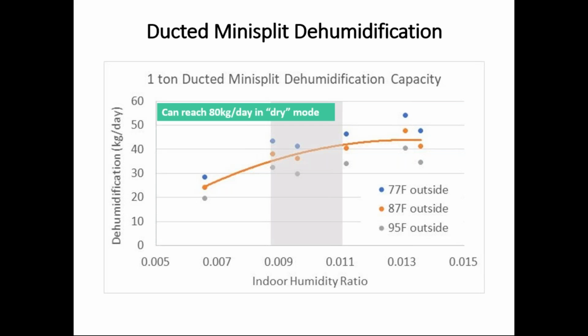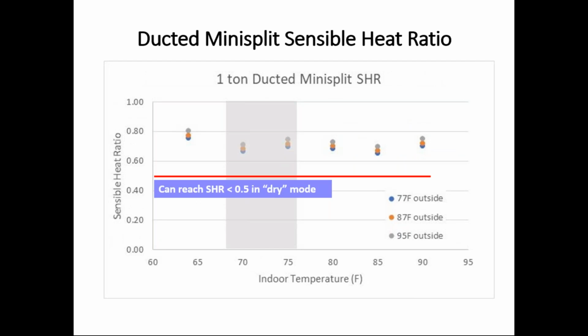The performance data for this mini split is somewhat bouncing around here, and that's because with today's inverter drives and variable speed fans, it has algorithms adjusting it. But roughly what you see is that it increases in humidity handling capability as the humidity ratio goes up. And then it drops off, or basically shifts more of its cooling capacity into sensible, as the humidity lowers, which is a trend that we like. As far as the sensible heat ratio, in typical operating conditions, most air conditioners operate with about a 70% sensible heat ratio, meaning that 30% of their capacity is going into dehumidification.